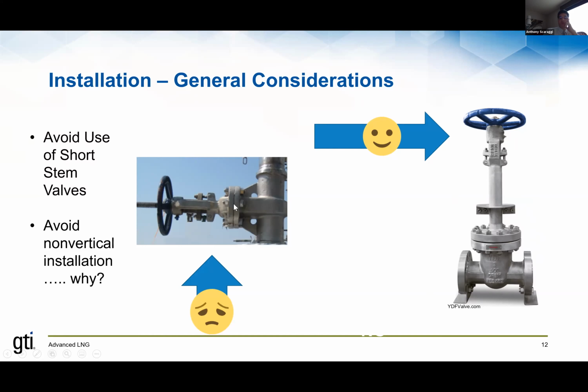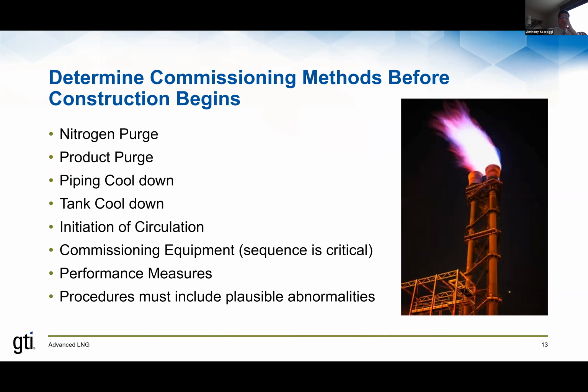If the valve is installed horizontally, you don't have the vertical space for the gas pocket to form and actually cause the seal. You'll always have liquid in this line, and you'll give yourself a point for leaks. So that's a design consideration in LNG facilities, and not just LNG facilities, any cryogenic facility.